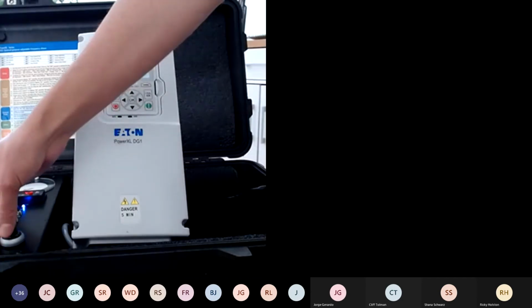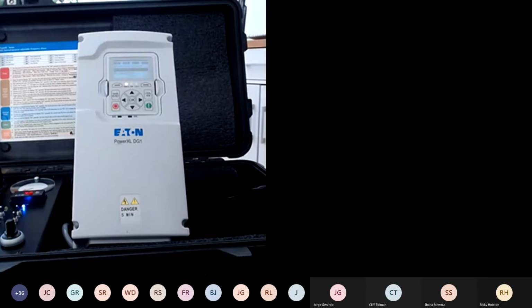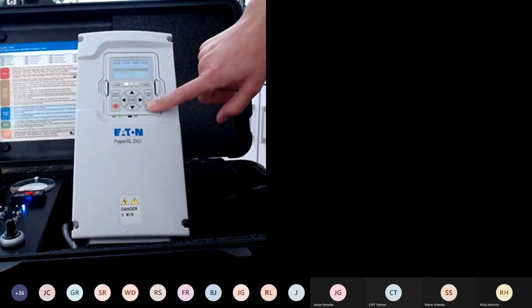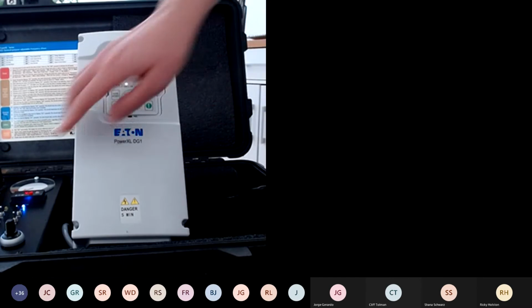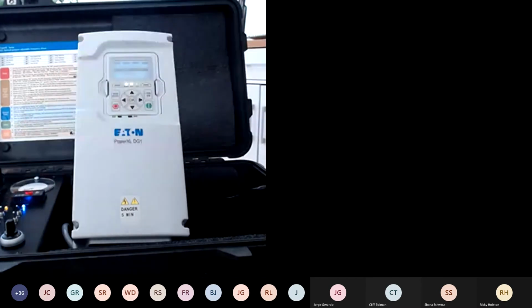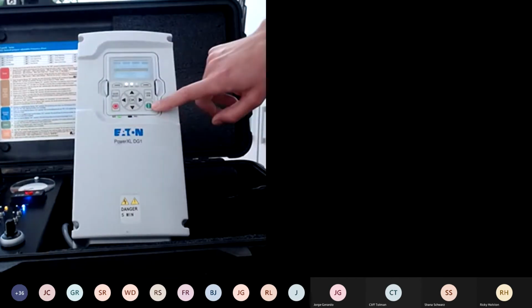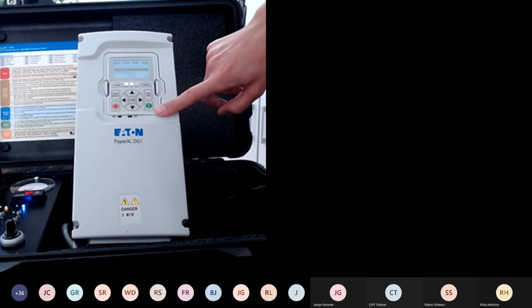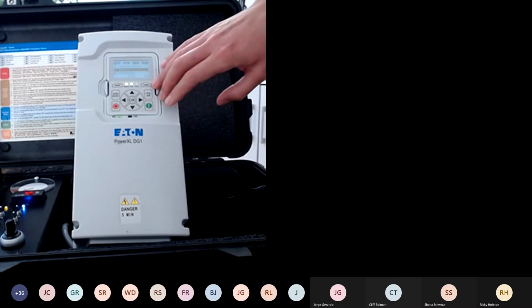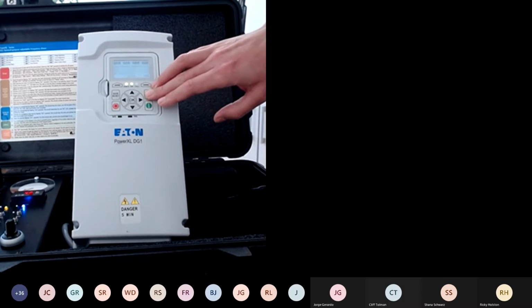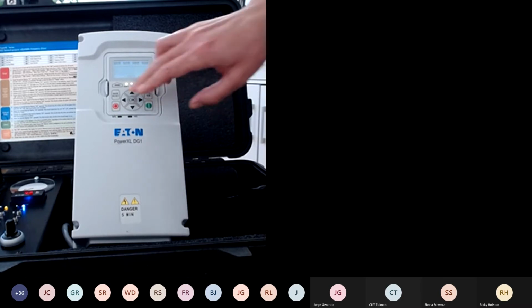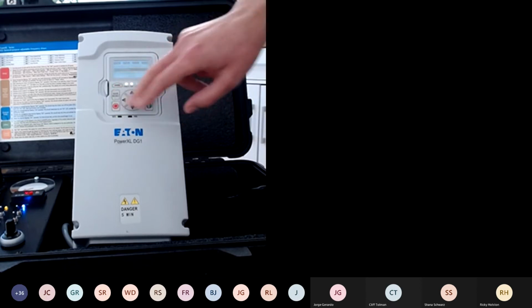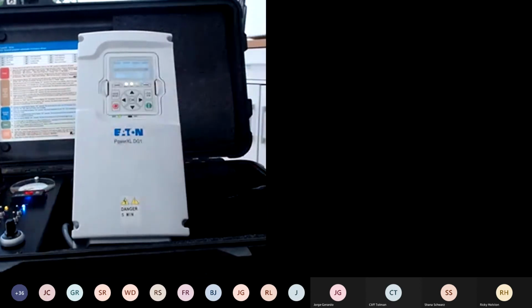So for here, you have digital input 1 as your start command. In order to start, you do have to reset the start signal. So for now, let's reset the start, make sure we are on remote control and start the machine. So let's go back to confirm that we have local, remote, back, and reset. And actually, it did send the signal to start, but what I actually forgot was to do the analog and be able to raise the speed of the machine.